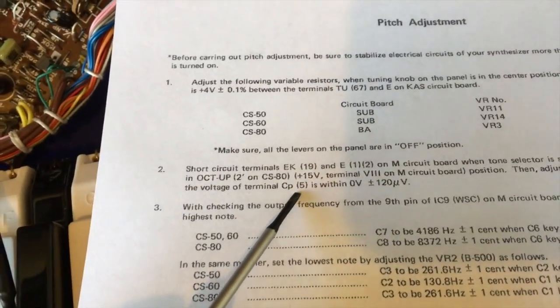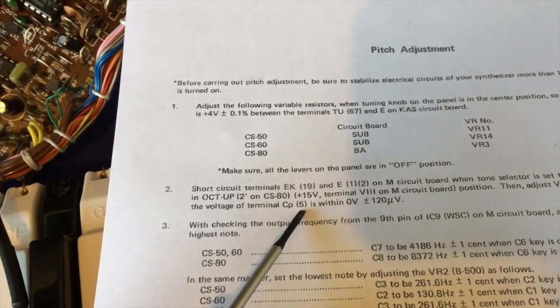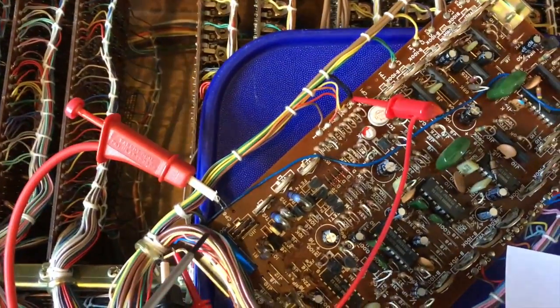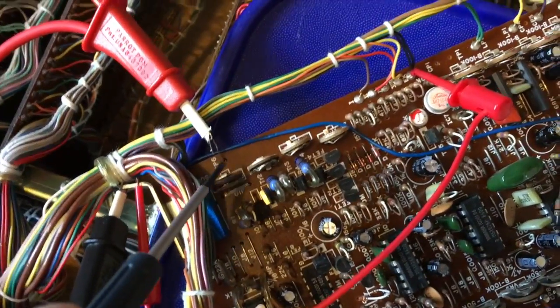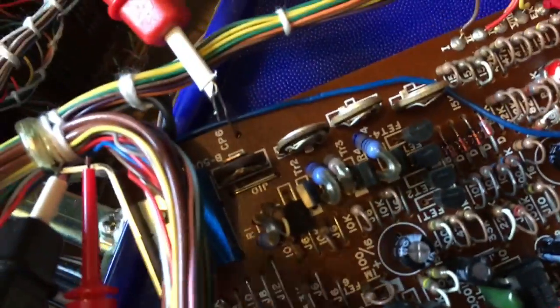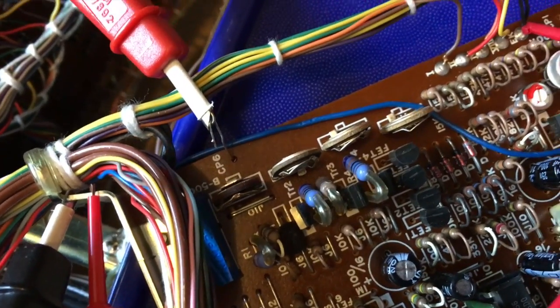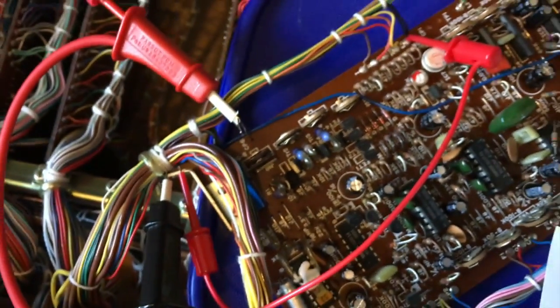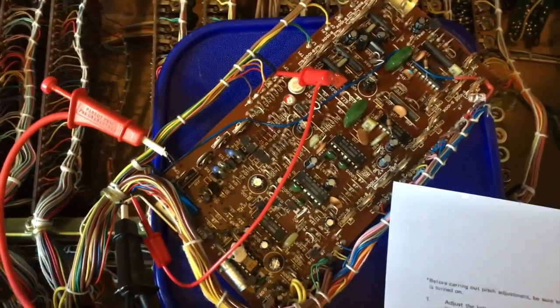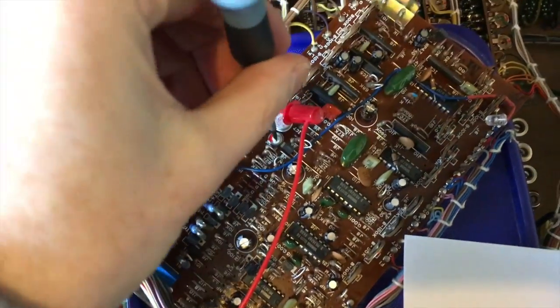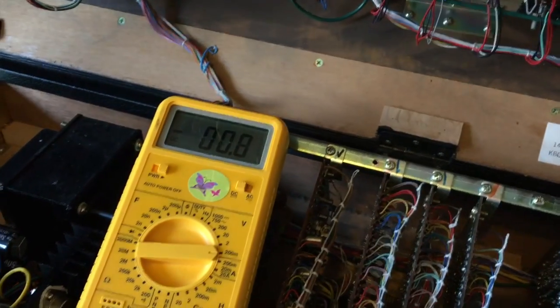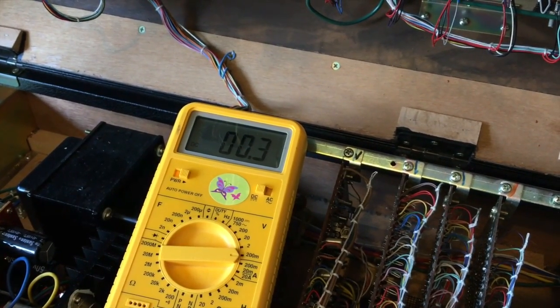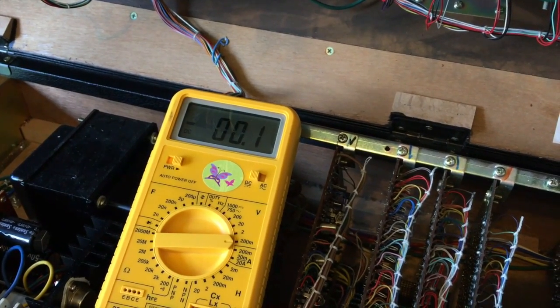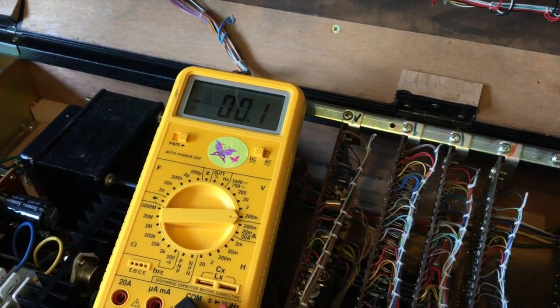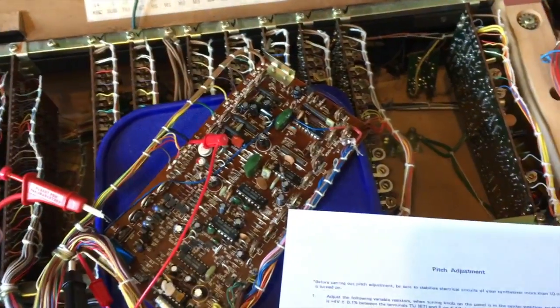It's not very well described in the manual. It actually tells you, just says CP and then 5 in brackets, which is pin 5. I've had a look at the schematics, and it's definitely this one. Now, I couldn't get my probe on there, so I've had to solder in another wire into CP5 so I could connect my probe to it. So what we need is this one to be 0. This pot here, it's very touchy. Mine was a little bit out. It was originally minus 1.7, and that's as close as I can get it because I've tried a few times already. So that's done. That's just the 0.